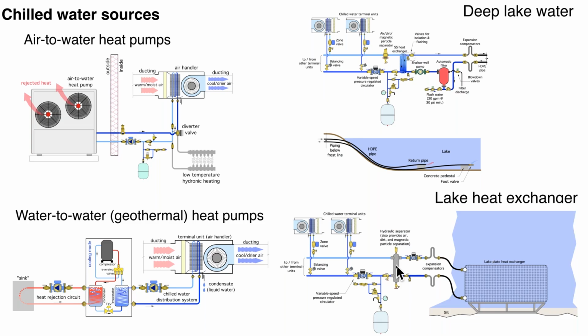Now we're using a hydraulic separator. We don't need to separate, from a purely technical standpoint, the water that is in the closed heat exchanger in the lake from the water that's going to go out through our cooling terminal units. Now, again, I would check if you're going to use an antifreeze in a system like this. Again, be sure that any environmental restrictions are addressed before you look at these. And obviously, the number of situations where you could use either of these lake water cooling systems is going to be more limited compared to what's over on the left side there, air to water or water to water heat pumps. But all of these are potential sources of chilled water for a small scale system.